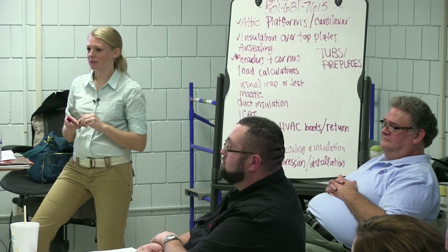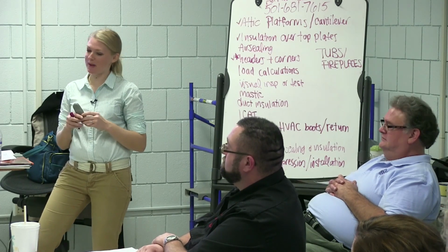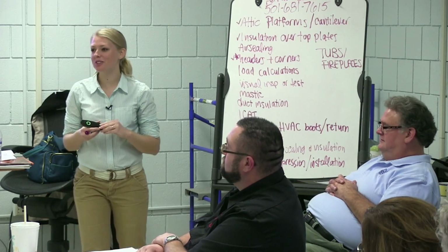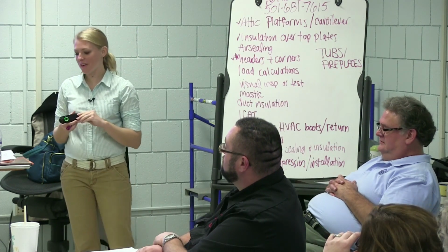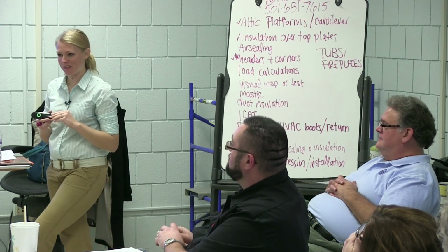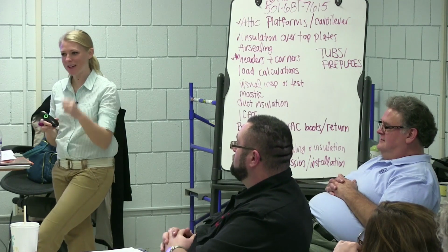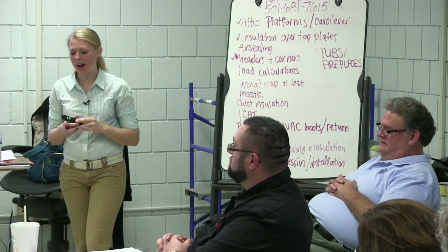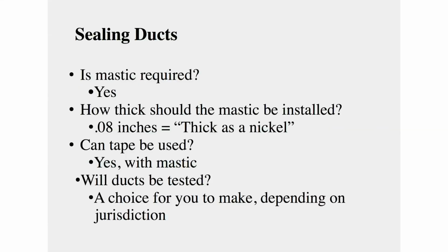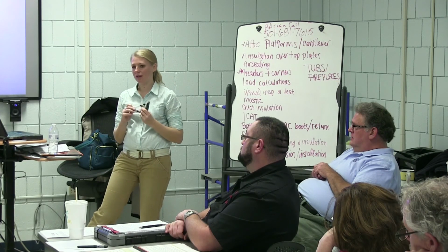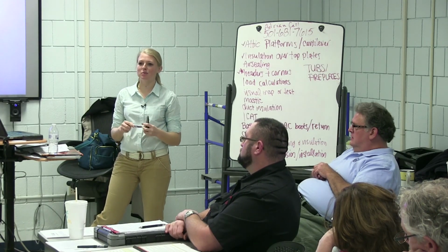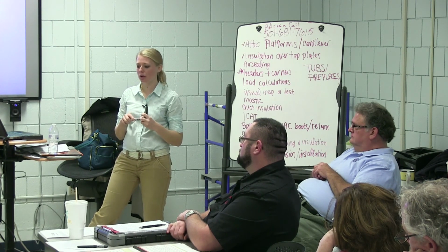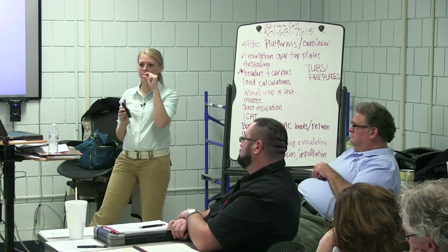But they leak bad. They do leak bad. In fact, I usually find that if a duct test is failing, that's the first thing that I'll go seal up. I'll go tape that up and see what happens. And how thick should the mastic be installed? According to this code language, 0.08 inches. What the heck is 0.08 inches? Are you going to get out your ruler? Good rule of thumb is as thick as a nickel.